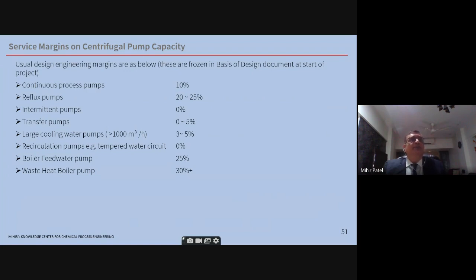Whereas, for example, a recirculation pump, for example a tempered water circuit, as I had mentioned with the earlier exothermic reactor, the pump goes to the cooler. You don't want to keep any extra capacity. You can have 0% capacity margin there. So these are the general industry engineering practices, basically. For normal pumps you keep around 10%, as is shown on the top.